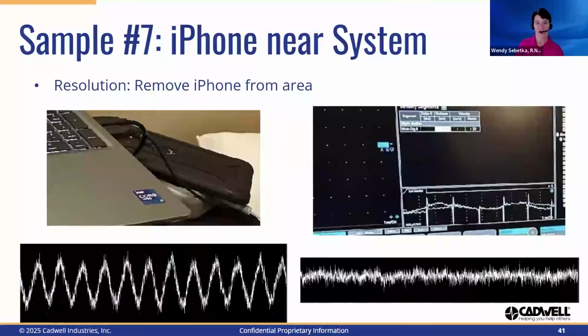Further observations of the area determined that when the coworker came in to review the study, they set their iPhone down near the system. The iPhone was removed from the device and the issue was resolved. It is important to note that while in this instance the phone was right near the device, this can also occur if the iPhone is in a pocket or being used. My observation has found that Android devices are not as bad as iPhones. I suspect this may be due to the iPhone design where the antenna wraps around the outer edge of the phone, pulling in more signals.